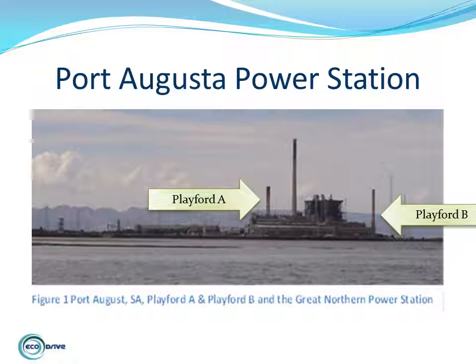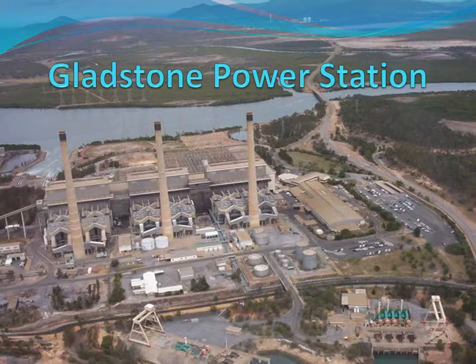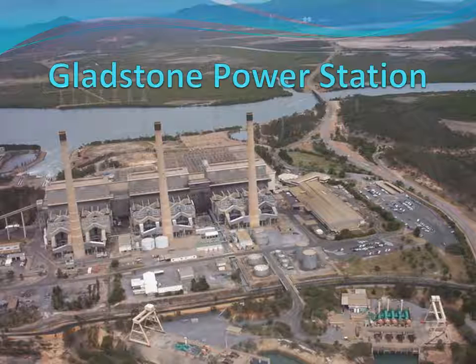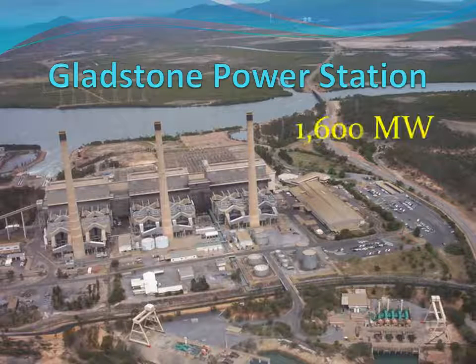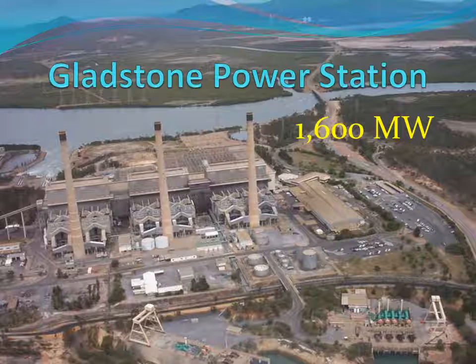Ideally, power stations are best located near the greatest load. However, this is not always possible. For example, Queensland's greatest load is located at Gladstone, with Queensland's largest power station at the Gladstone Power Station, generating 1,600 megawatts from 6 coal-fired boilers. Queensland's second largest load is located 900 kilometres to the north at Townsville. The power stability at Gladstone is far better than that at Townsville, and the transmission costs much lower. On the other hand, power stability is an issue at Townsville at times.